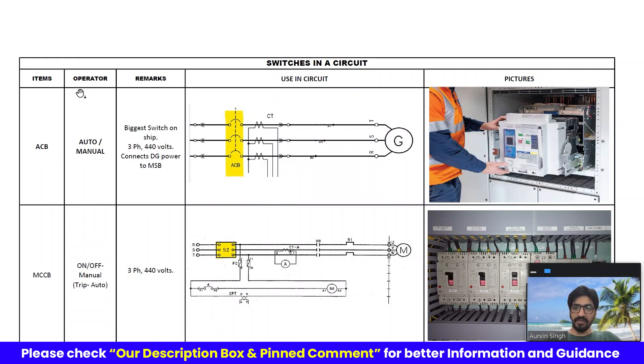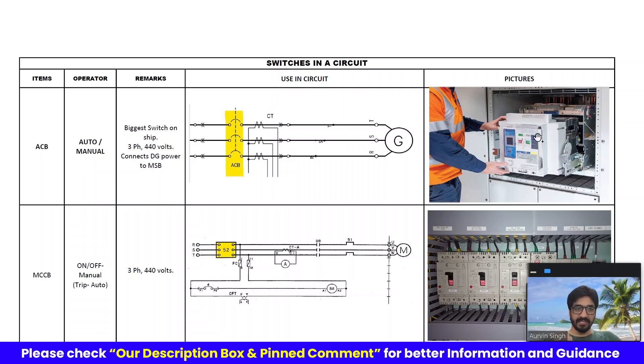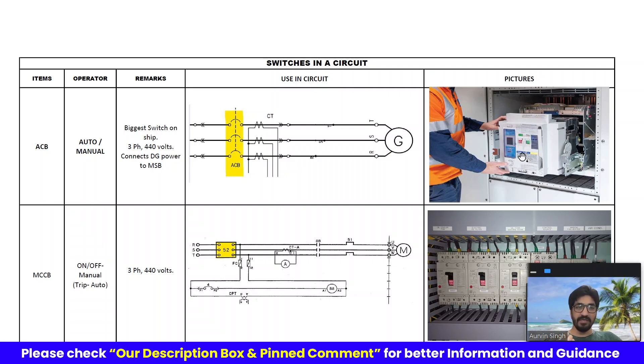How do we operate this? How is it switched on and switched off? Well, this is operated either automatically or manually. We can just push a button on top of it — manually we can push the button on and off. However, it also happens automatically because inside there's a control arrangement with some coils — closing coils and trip coils or under voltage coils — which help operate this switch.